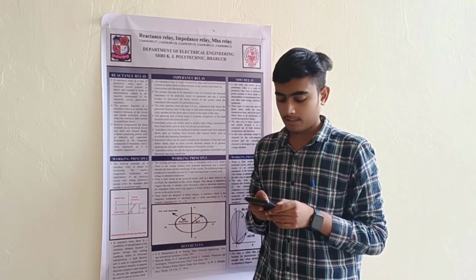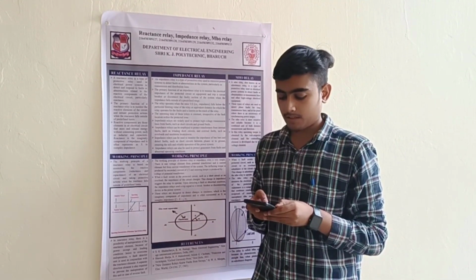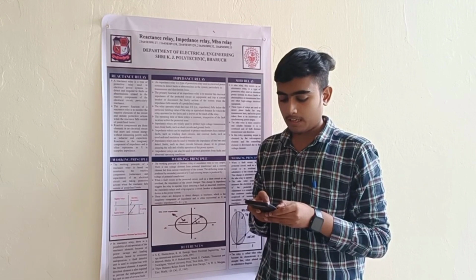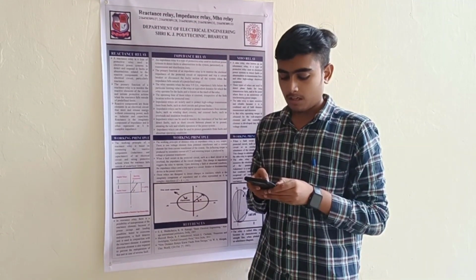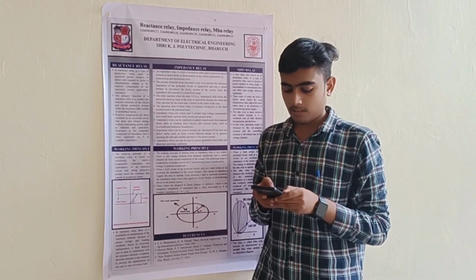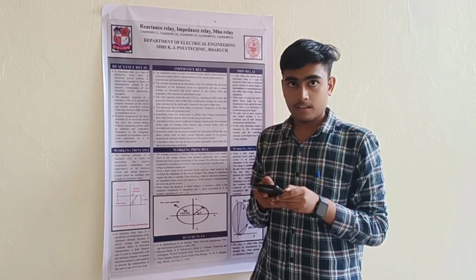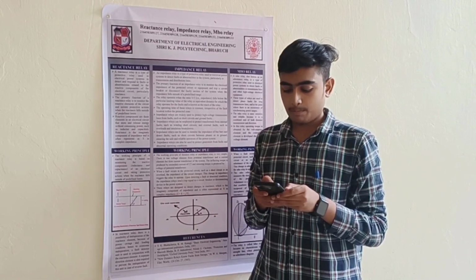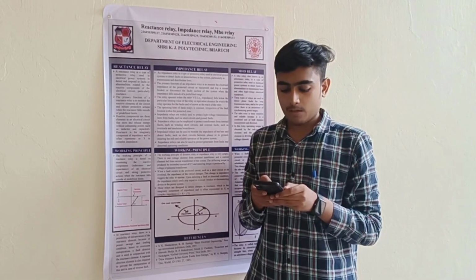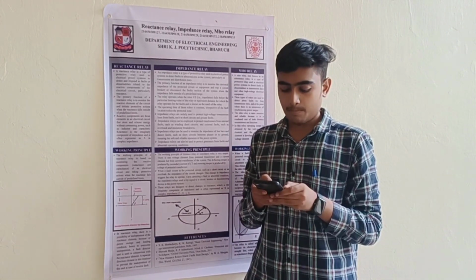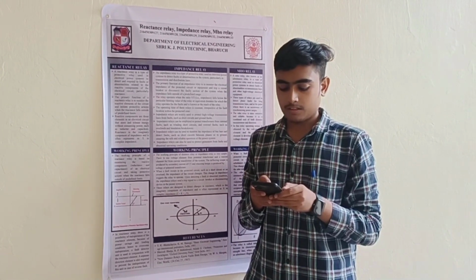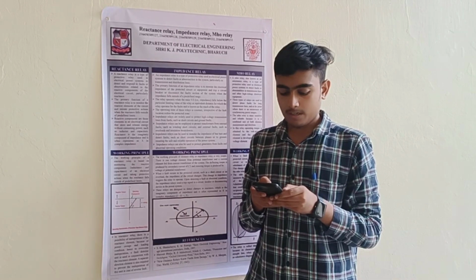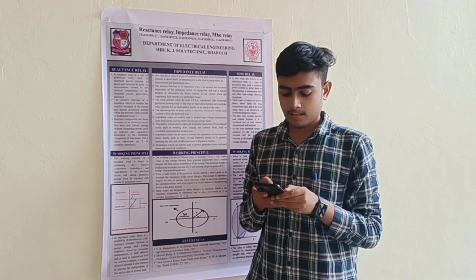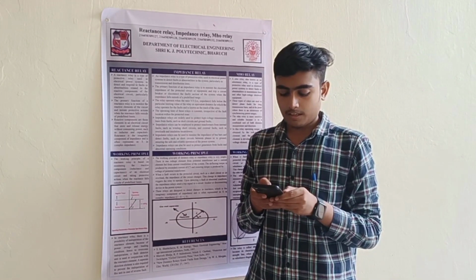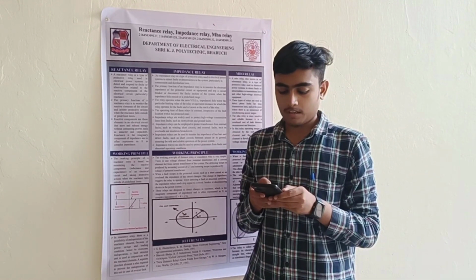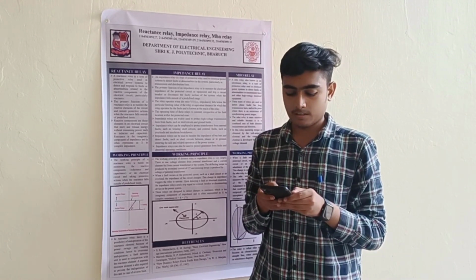First, fault detection and isolation. The primary application of the Mho relay is to detect and isolate faults in transmission lines. It measures the impedance of the line and compares it with the predetermined set value. If the impedance falls outside the set range, indicating a fault, the relay operates and initiates the tripping of the circuit breaker to isolate the faulty section.